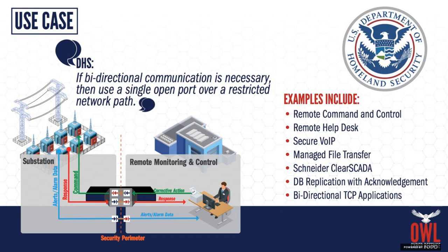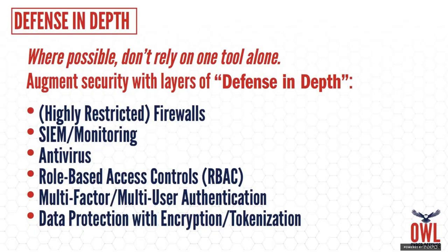It's different than a firewall, because in a firewall, of course, you're opening up a connection. It's still a routable connection, and whatever traffic goes across it goes across it. But here, we're still doing the protocol breaks. The outside can't see the inside, the inside can't see the outside. Nothing routable traverses, and it's just payload moving back and forth. Okay.